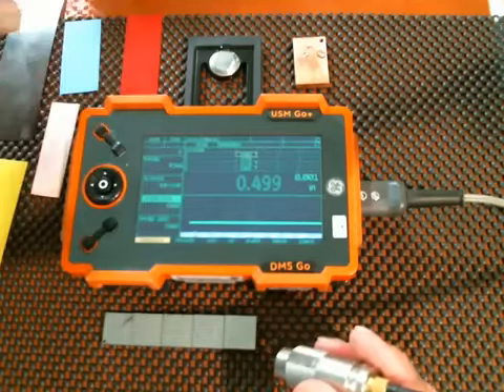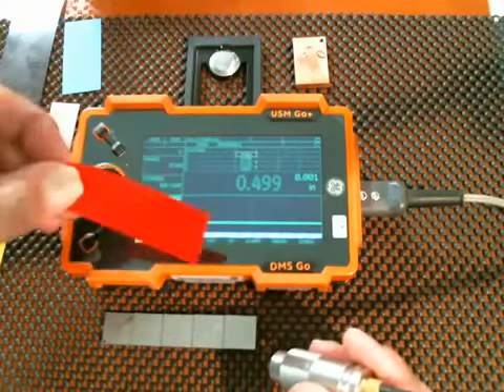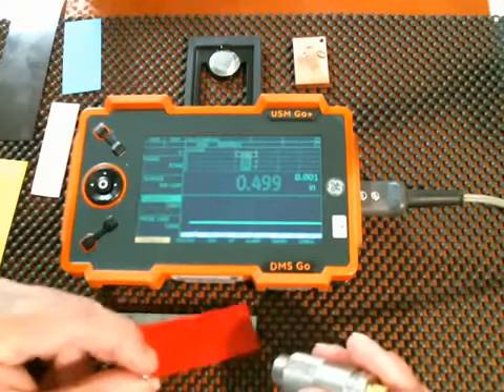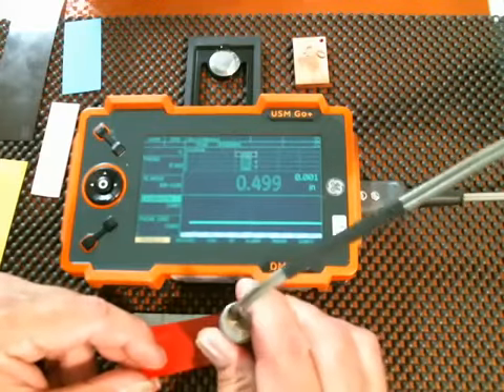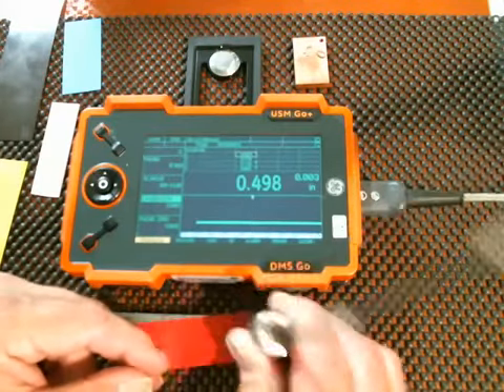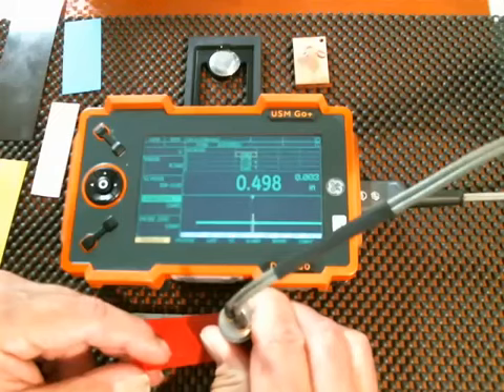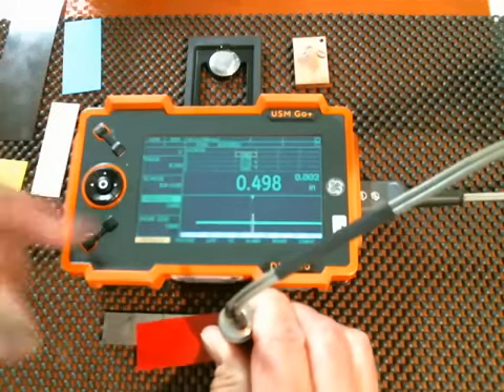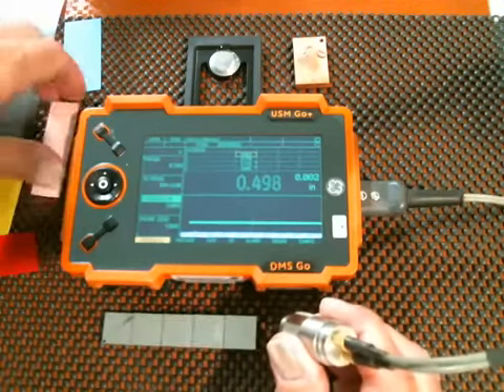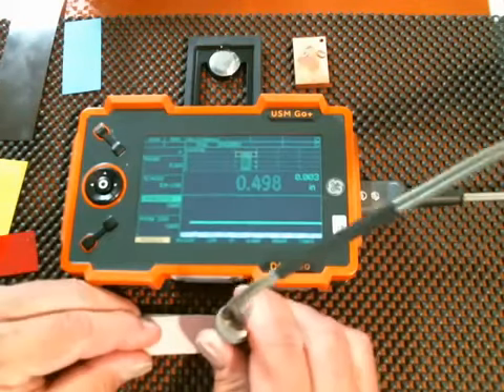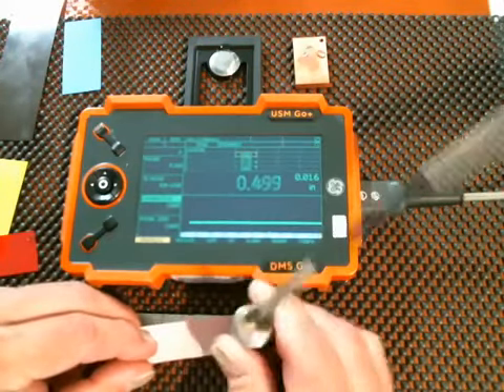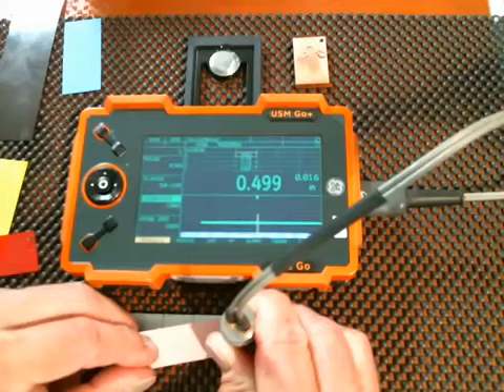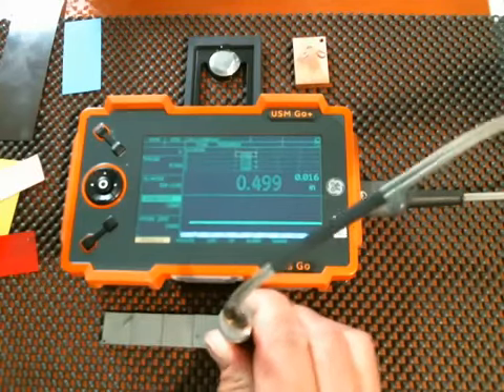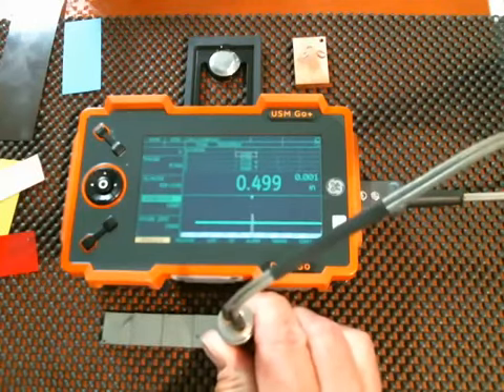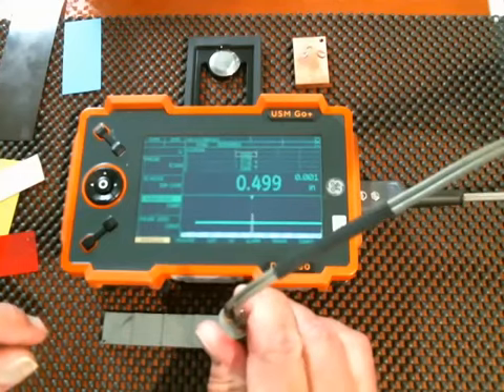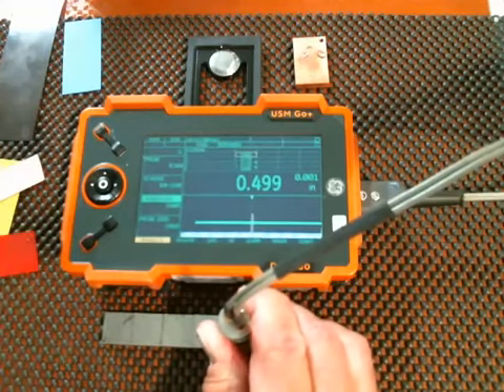I have some plastic shims here of varying thicknesses. My red shim is 2/1000. So if I put that on the 1/2-inch block, I've got a little bit of variation from couplant and squeeze out and so on, but 1/2-inch, 3/1000 thickness. Pink shim is 15/1000. I'm showing up just a little bit thick on the coating. I'm showing 16/1000. So I'm off by about 1/1000, which is within the tolerance of the instrument.